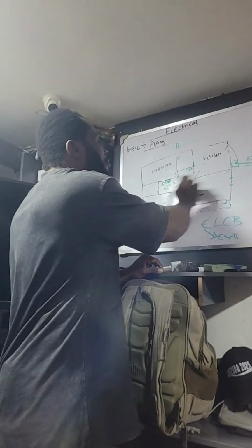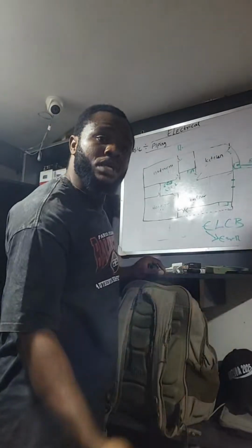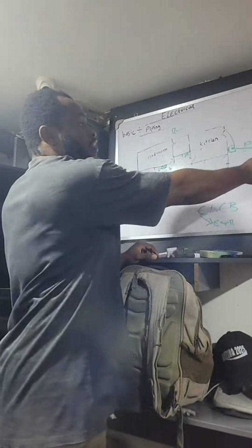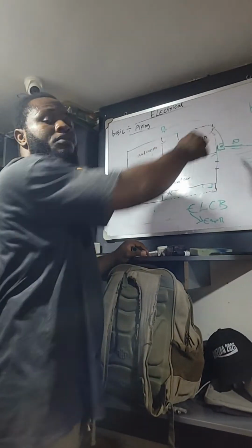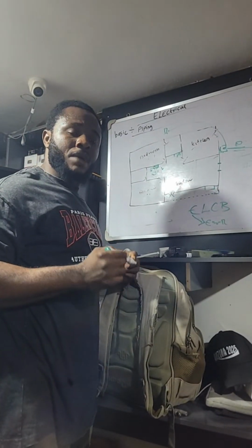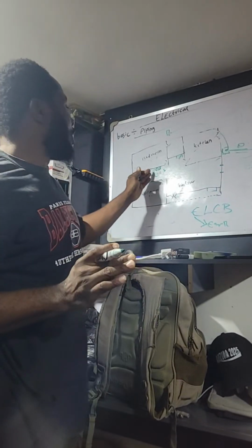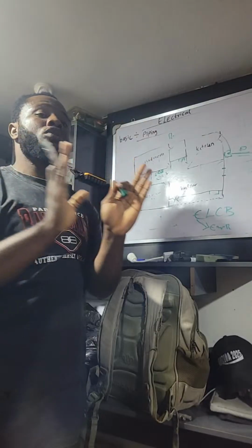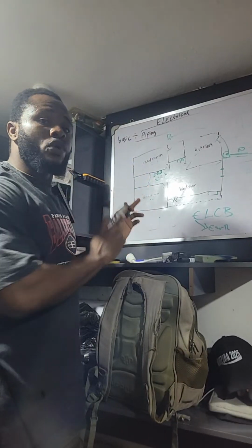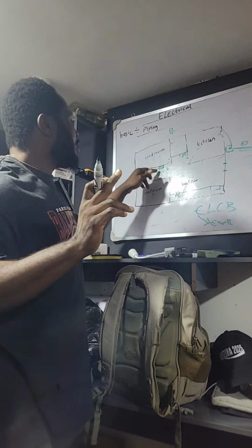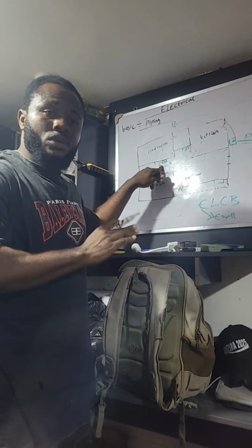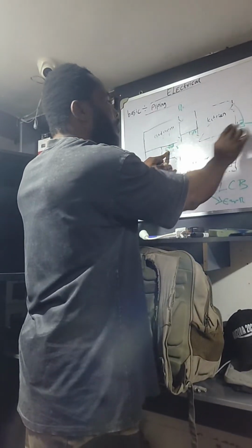Even if you still want to use 16, it would still be less. You understand? Compared to the price of buying armored cable, drawing here and merging them together. Am I communicating? So that's why we don't put ELCB here. We put our own outside because it's a two-way protection now. It's the load line protection and the inner load protection. What I mean by load line protection is the cable they run from this DB point down to where our ELCB is.